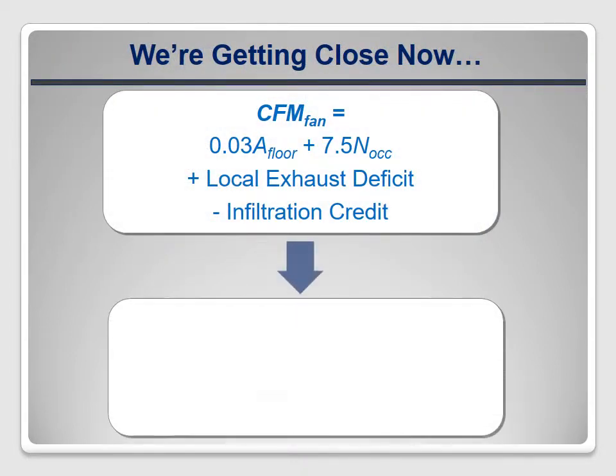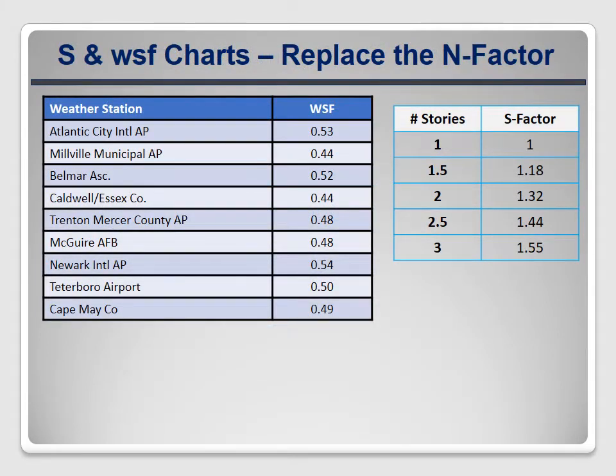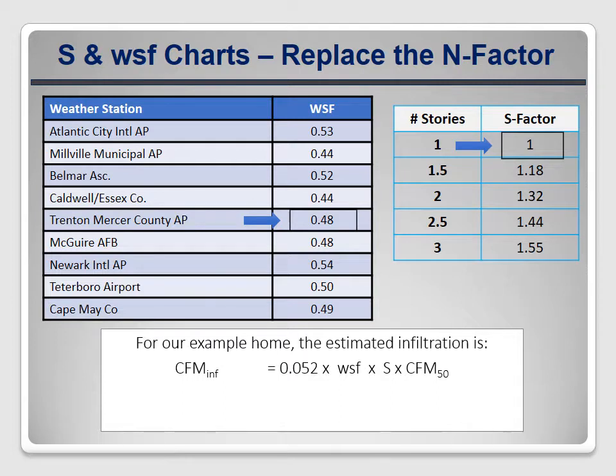The base formula gave us a total required ventilation rate of 74 CFM, and the shortfall in local exhaust means we add another 5 CFM to compensate. Now all we need is the infiltration credit. For our example house, the weather and shielding factor (WSF) is 0.48, based on the closest weather station in Trenton, and the S factor is 1 because it's a one-story house. Plugging those into the equation with the blower door reading: estimated natural infiltration = 0.052 × 0.48 × 1 × 2000 CFM = 50 CFM. That's our infiltration credit.